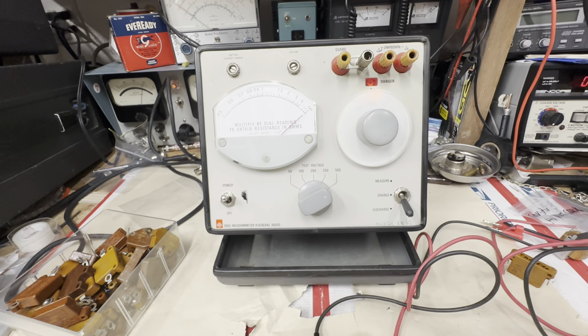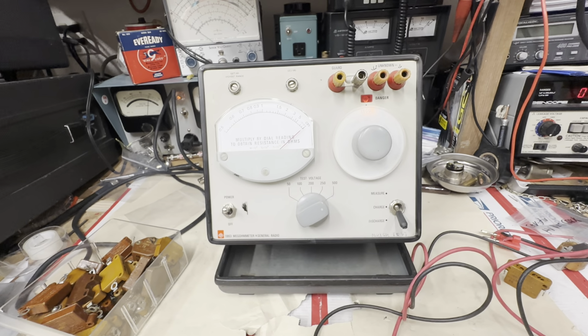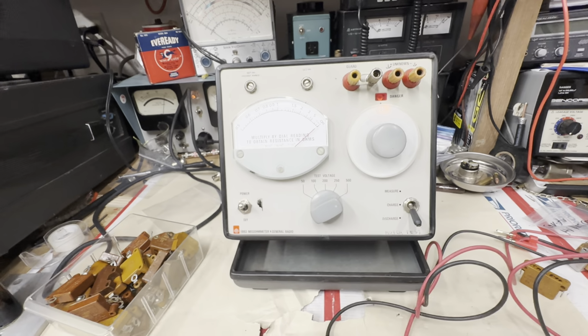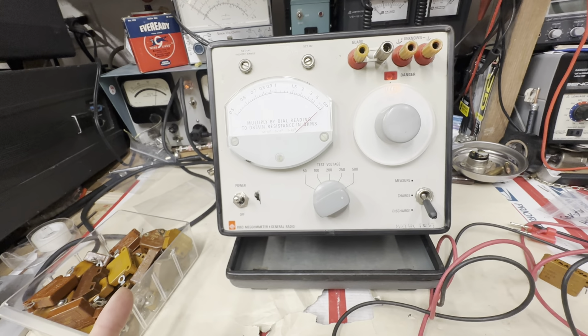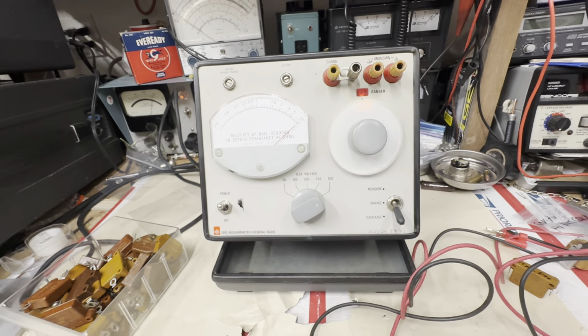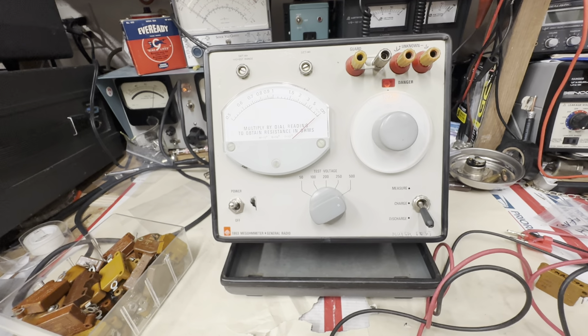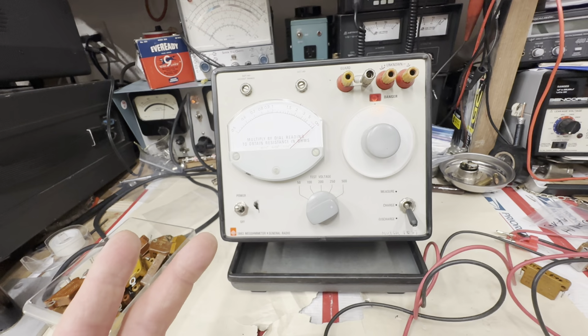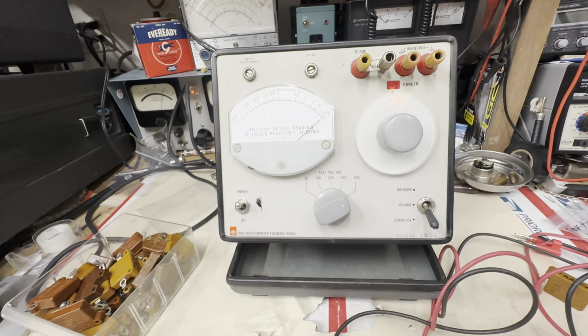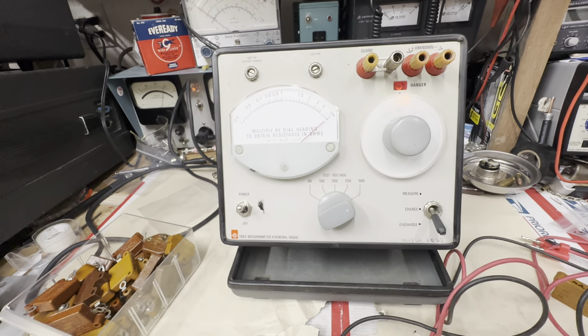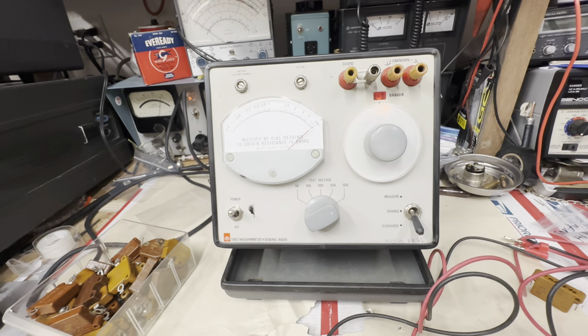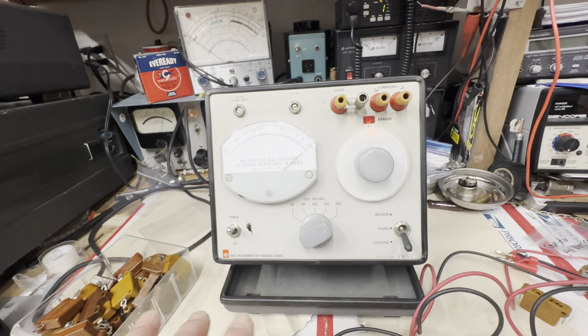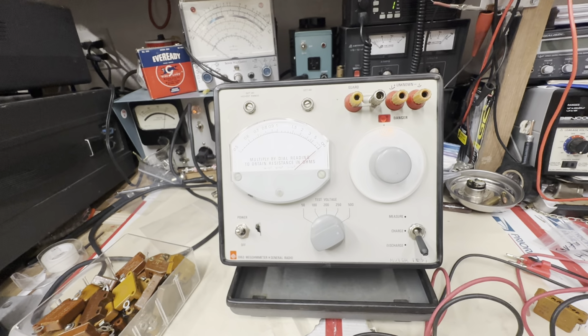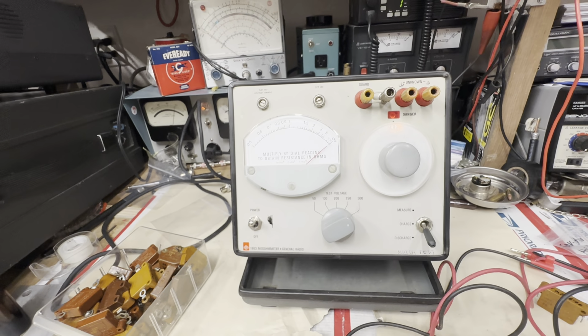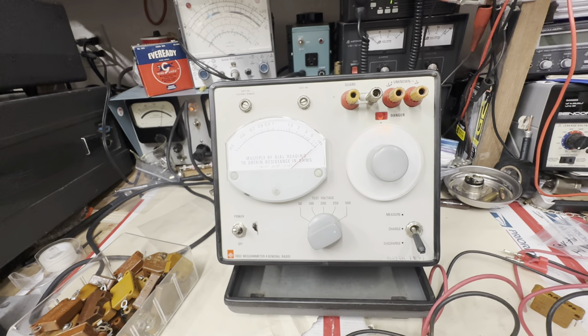My rule of thumb is you have to have 3 of each of everything. You got one that you normally use. Well, if it breaks, you have to have one to calibrate it against or to check it against. And then do you know whether that one works or not? So you have to have another one laid back again so you can fire that one up. And then when 2 of the 3 match, those are 2 good ones. And the one that doesn't match, that's the bad one. So you have to have at least 3 of every piece of test equipment.